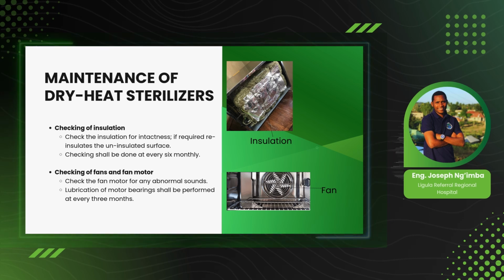Another thing we do in maintenance is to check the fan and the fan motor. In checking the fan and the motor, we want to check whether the fan rotates abnormally. If there is any abnormal sound, it means the fan is at a different angle, which, as we will see in the troubleshooting part, can cause variation of temperature. So the fan must stay in its position and rotate as required. Also, we check the fan motor so that we can lubricate the bearings of the motor to reduce the abnormal sounds that you can hear while the machine is working. This kind of maintenance we do on a 3 months basis, or quarterly. Here in the picture, we can see the fan very clearly, where it is located. Its function is to circulate the hot air within the chamber.